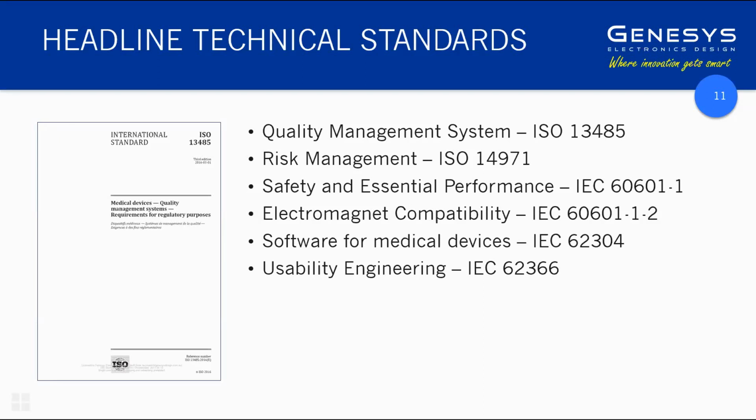And if you're going the in-house route, you'll certainly need to have that in-house. What makes it really easy is if all of the companies that are providing services to you, like your electronics designer, your industrial designer, your manufacturer, and so forth, are also ISO 13485 certified for their particular aspect, so Genesys is for design only, CircuitWise is for manufacturing only, and so forth. If they've already got these systems in place, it makes the process of having your product certified at the end of the day a lot easier. Can you explain that, Jeff?